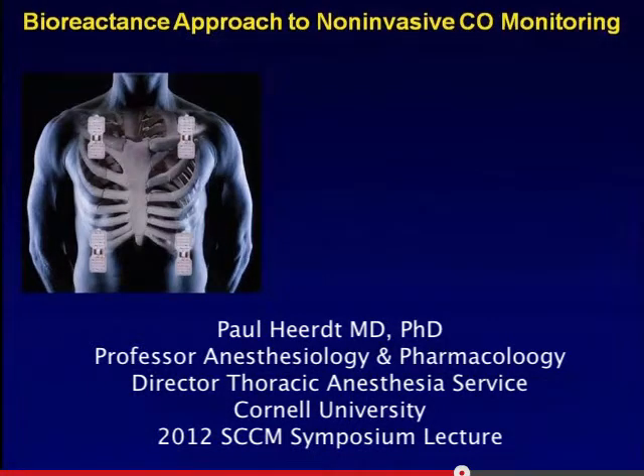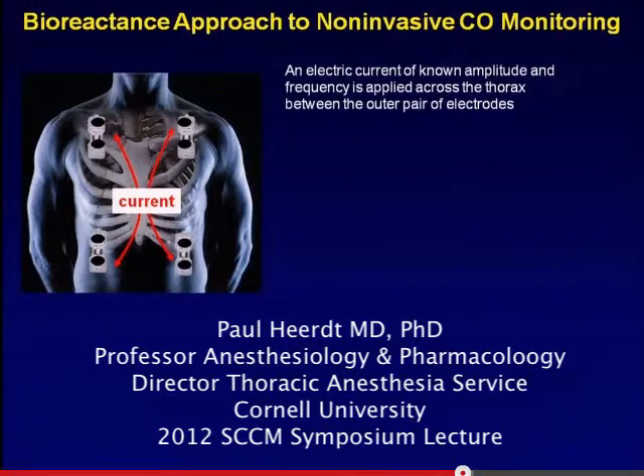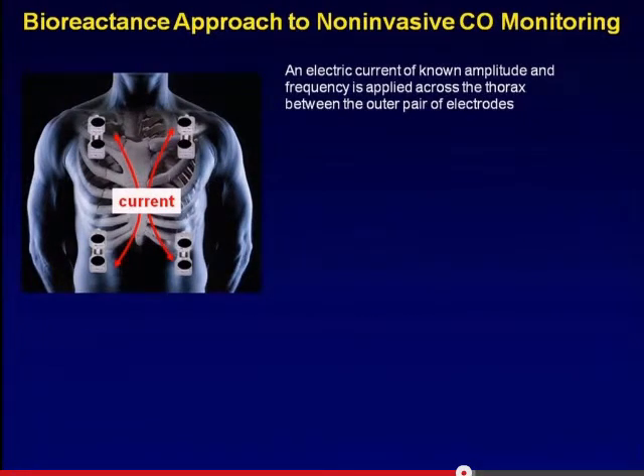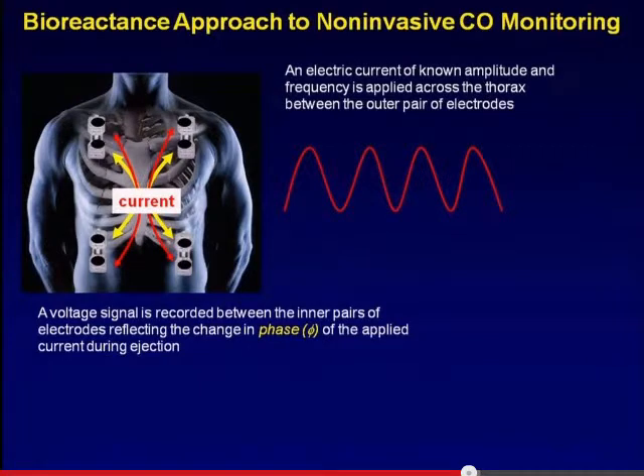Now, as we've seen already a little bit how the device works, there's the electrodes that are placed. Each electrode has 2 sensors in it, an inner and outer sensor, and a current is applied from the outer sensors. It's very cleverly done. There's actually 2 sets of measurements, one from each side of the body. On each of these sensors, there's an inner set of electrodes, and the outer electrodes provide the current, shown with a known frequency in red, and the inner ones sense this current. So the signal actually comes with what they described as the phase delay here.